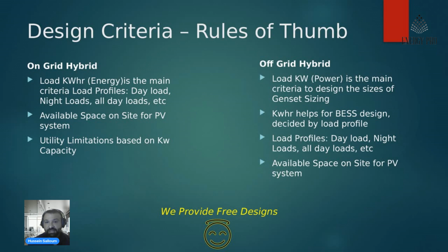Here we have to look at the space. If there's enough space, we can put in the full amount. If there's not enough space, we have to check how much we can put, and the balance has to be covered from the grid. Here, it's very important that we take approval, because if it's an on-grid system, we take the approval of the utility on the percentage of PV that we can put. And of course, the generator will be designed based on the final criteria, how much PV we put and how much space is available, and then we can size. Now, the generator is always flexible. In the case of the grid, it's up to you to decide how much you put based on the load profile.